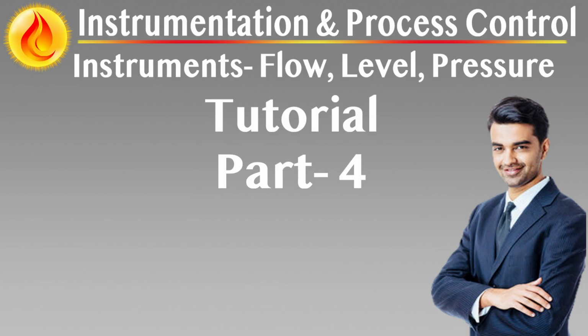Maintenance and calibration considerations. PD meters require routine inspection and periodic recalibration, especially in fiscal service. Wear of internal moving parts can lead to drift over time, particularly in non-lubricating or abrasive services. Many units include mechanical calibration mechanisms or adjustable gears for field tuning. For critical accuracy, proving systems such as compact provers, master meters, or tank provers are used to verify meter performance. Proving may be continuous or periodic, depending on contract or regulatory requirements.